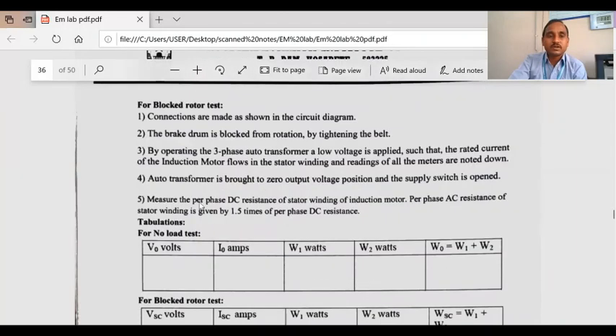So similarly for the blocked rotor test, the connections are the same. The only thing is the brake drum is blocked from rotation by tightening the belt thread. Okay, and next by operating the three-phase auto transformer, a low voltage is applied. What does low voltage mean? It is such that the rated current of the induction motor flows in the stator winding, and the readings of the meters are noted down. Okay, then the auto transformer is brought to zero output voltage position and the supply switch is opened.